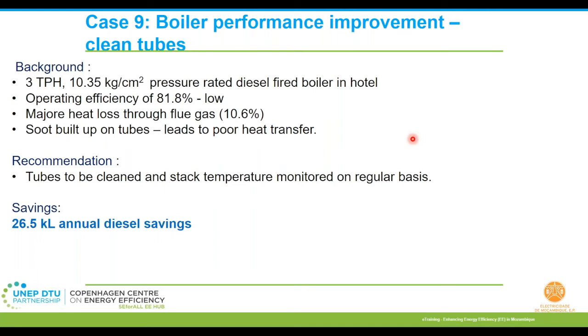So it was a simple measure. What we asked them to do is first clean the tubes, and in order to take care of this maintenance, regularly keep monitoring the stack temperature. If the temperature goes beyond a certain point, then it is time to clean the tubes, rather than waiting for a quarterly schedule of operation and maintenance measures. So it's better to take a dynamic approach than a passive approach of maintaining a scheduled timeline. This way, they were able to save about 26 kiloliters of annual diesel consumption.